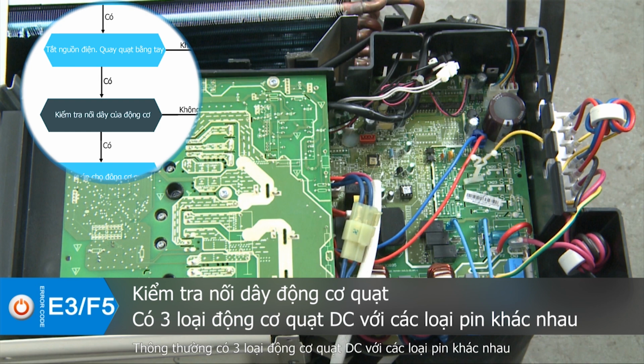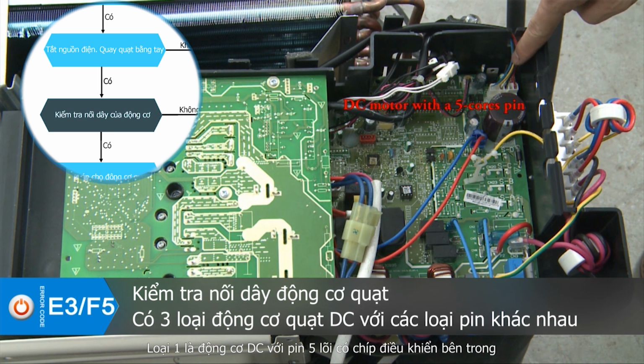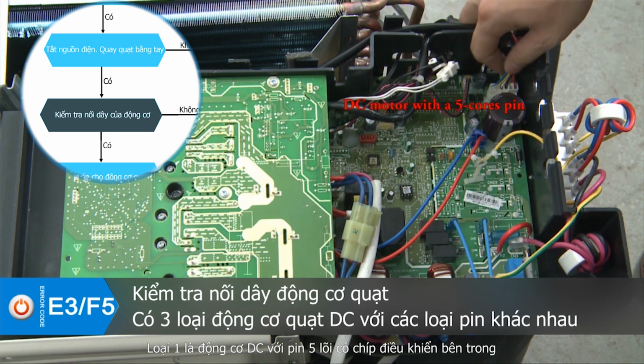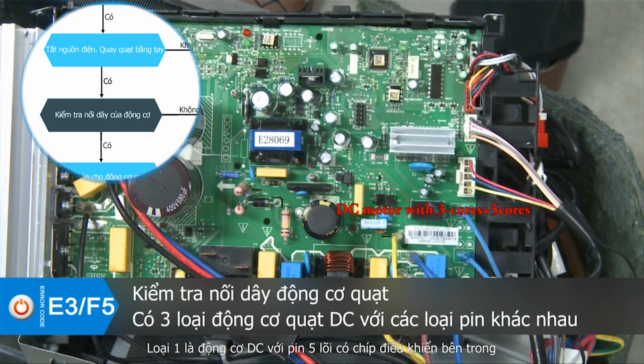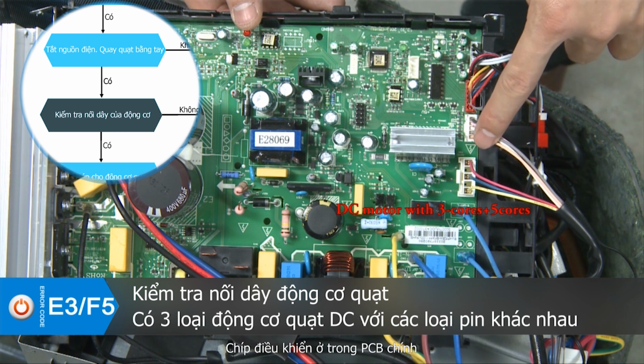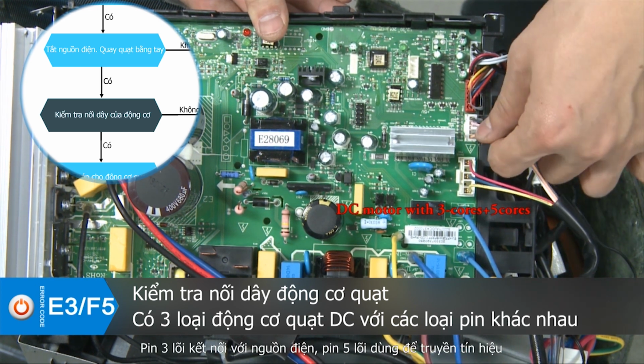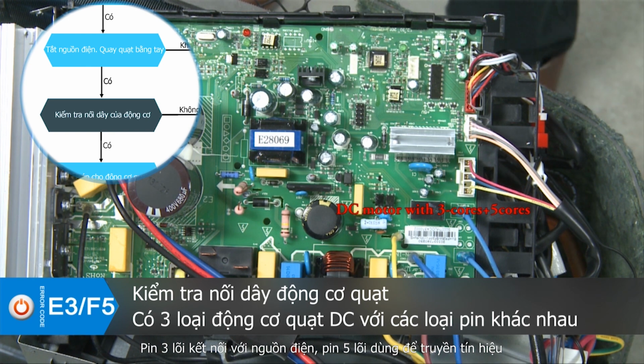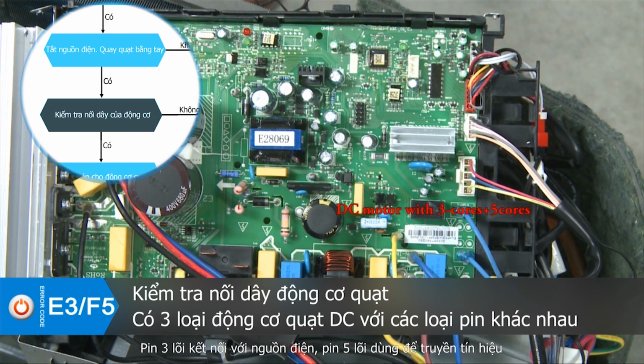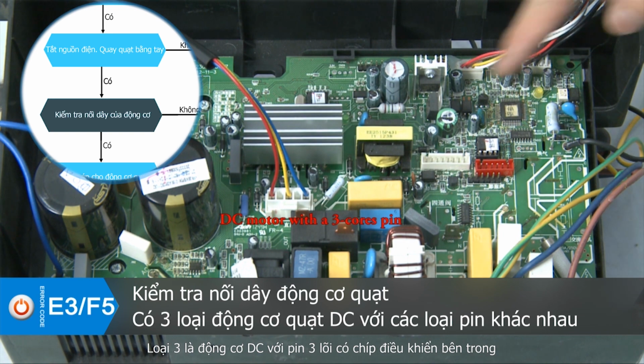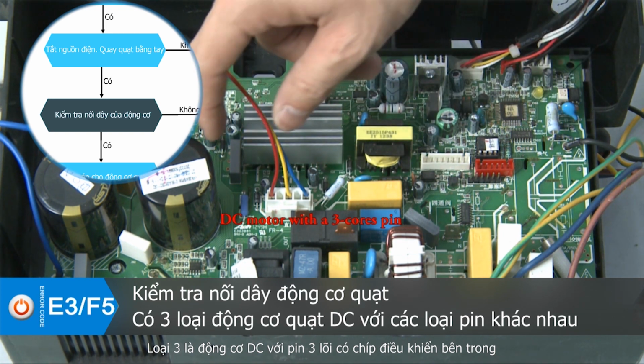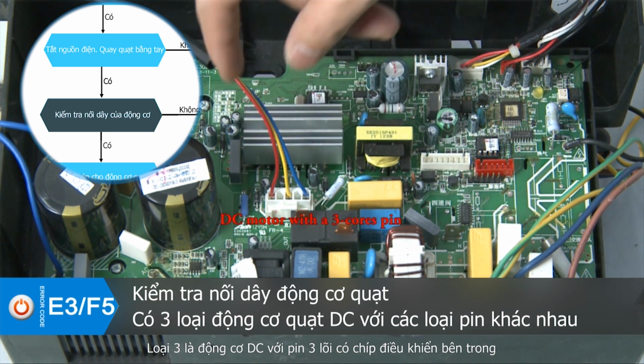Commonly, there are 3 kinds of DC fan motors with different pins. First, DC motor with a 5-core pin, which has a control chip inside itself. Second, DC motor with 2 pins, a 3-core pin and a 5-core pin. The control chip for it is on the main PCB board. Separately, the 3-core pin connects to the power supply, and the 5-core pin is used for signal transmission. The third is DC motor with a 3-core pin, which has the control chip in itself.